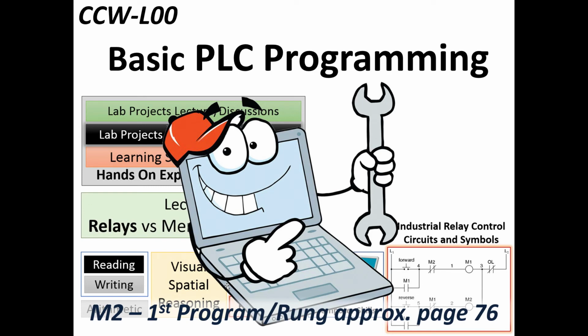Ladder logic diagrams do not exist in the controller, nor do function block diagrams or structured text. What gets downloaded to the controller, if you want to call it a program, is in machine level language. So what you're looking at on your screen is a graphical representation of the logic that's in the controller, animated by the state of the bits and words in memory of the controller.